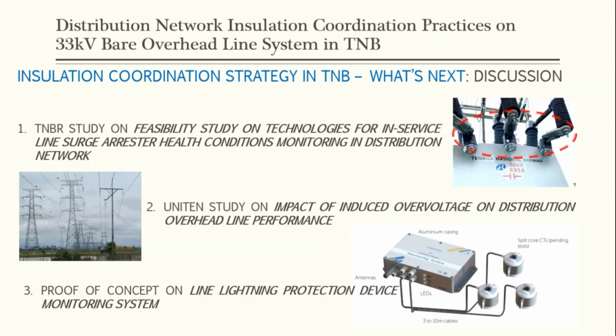And secondly, we have a UNITEN study on impact of induced overvoltage on distribution overhead line performance. We have a lot of distribution lines sitting next to transmission lines. So we want to study whether there is any induced overvoltage issue. And if there is, what can we do to minimize the induced overvoltage issues in distribution overhead line performance? And thirdly, a proof of concept of the lightning protection device monitoring system.